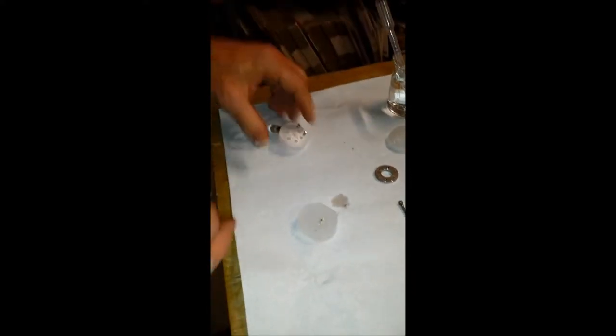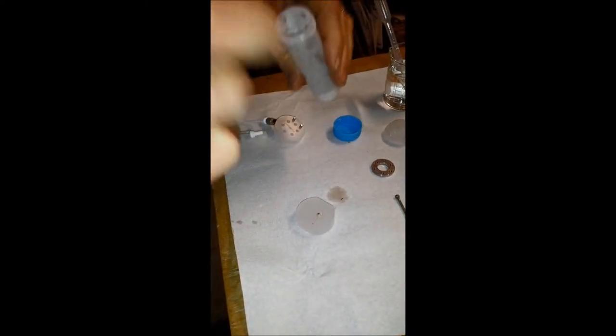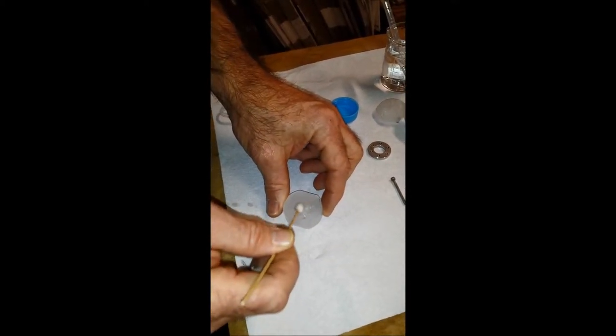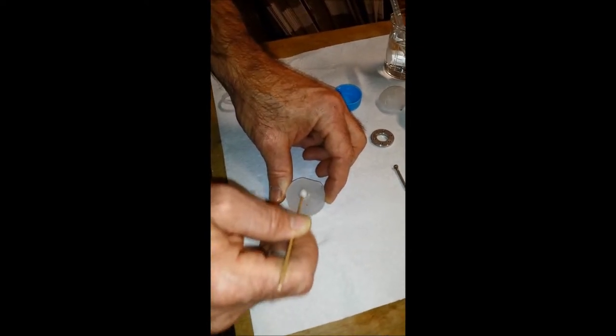A quick way is to put a ball of water onto the working electrode, which is silver, and use a small amount of a polishing compound and lightly go in a circular motion, very lightly.